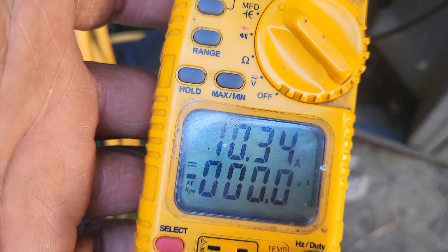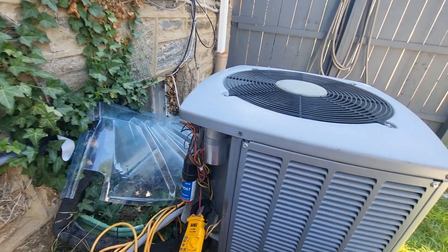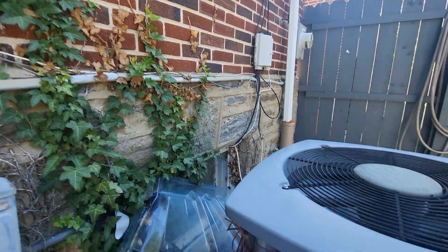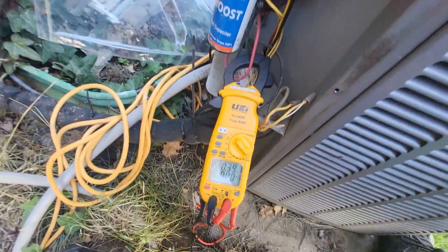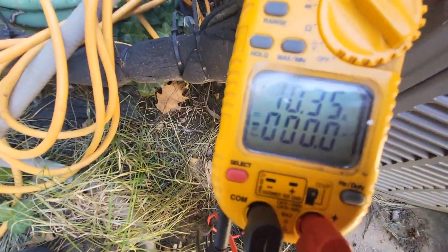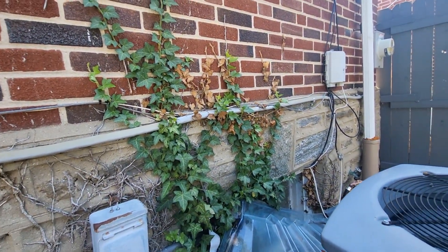Let me clean out the electrical components. All right, guys — this is definitely well below threshold. But this customer did get a bunch of electrical work done: I think he got a generator put in and some type of attic fan. I told him over the phone we can isolate the AC, make sure the amp draw is normal — nothing looks abnormal, the breaker is the right size. But lights flickering could be an issue with the wires, and that would definitely be an electrician's area. They can isolate the circuit and lead him in the right direction.